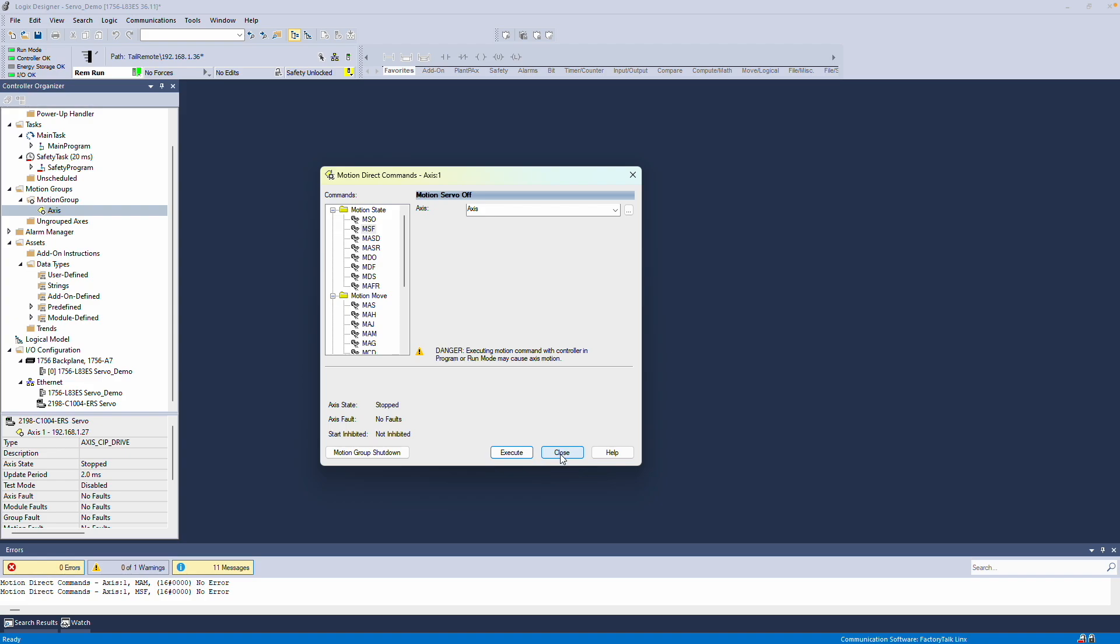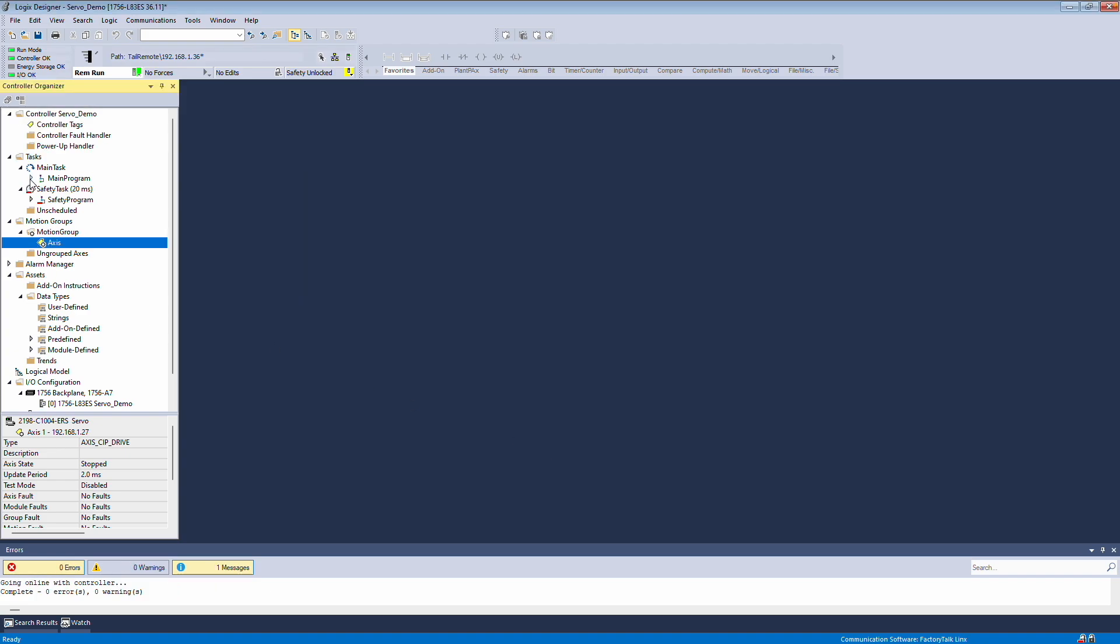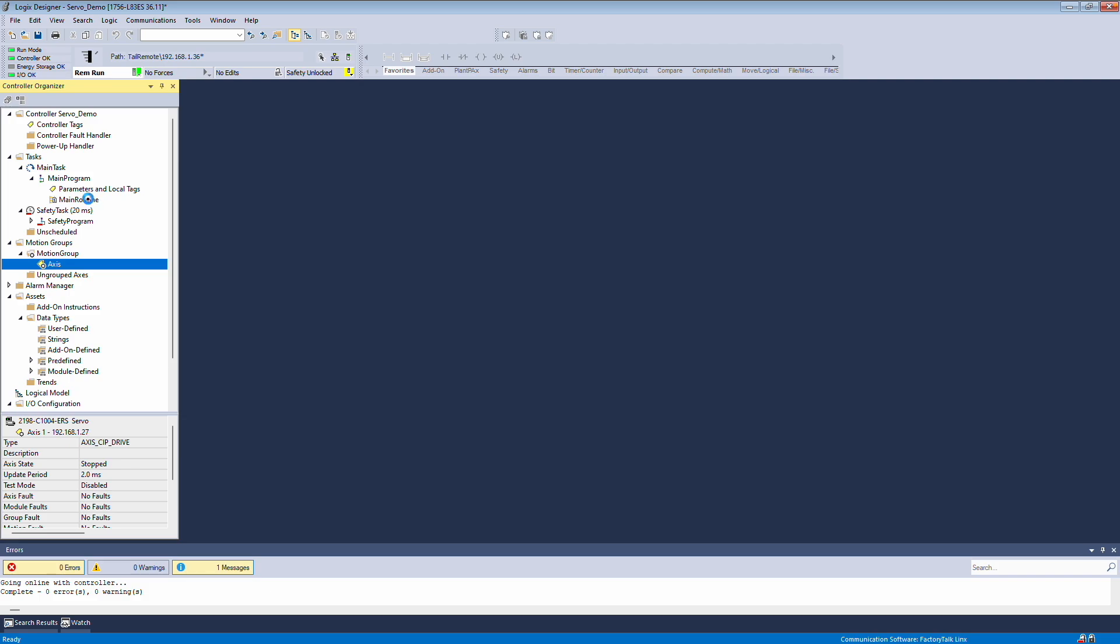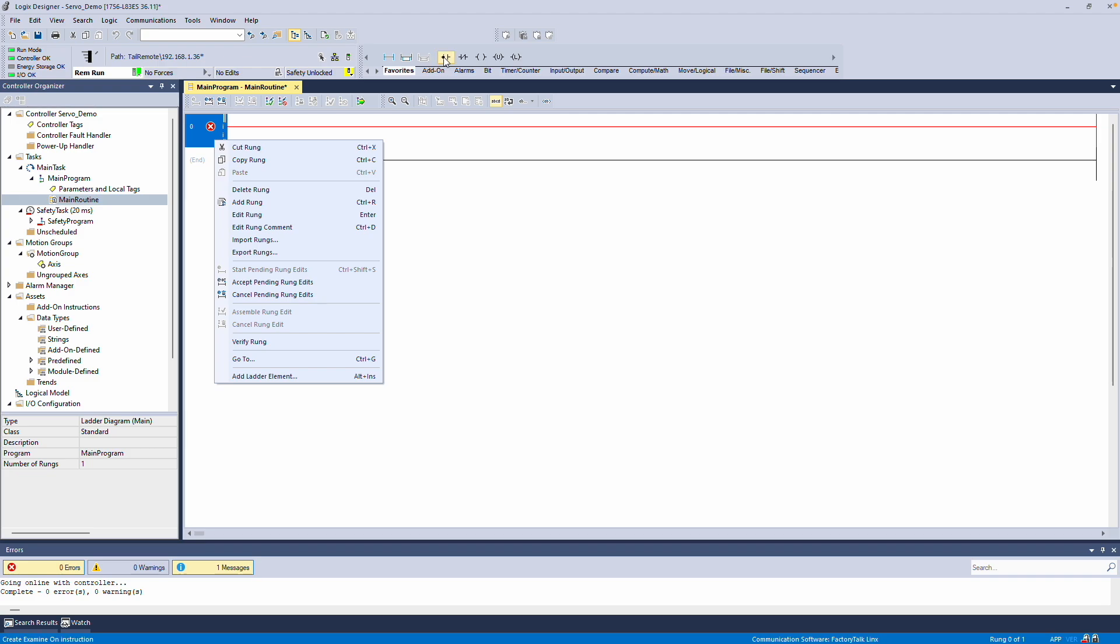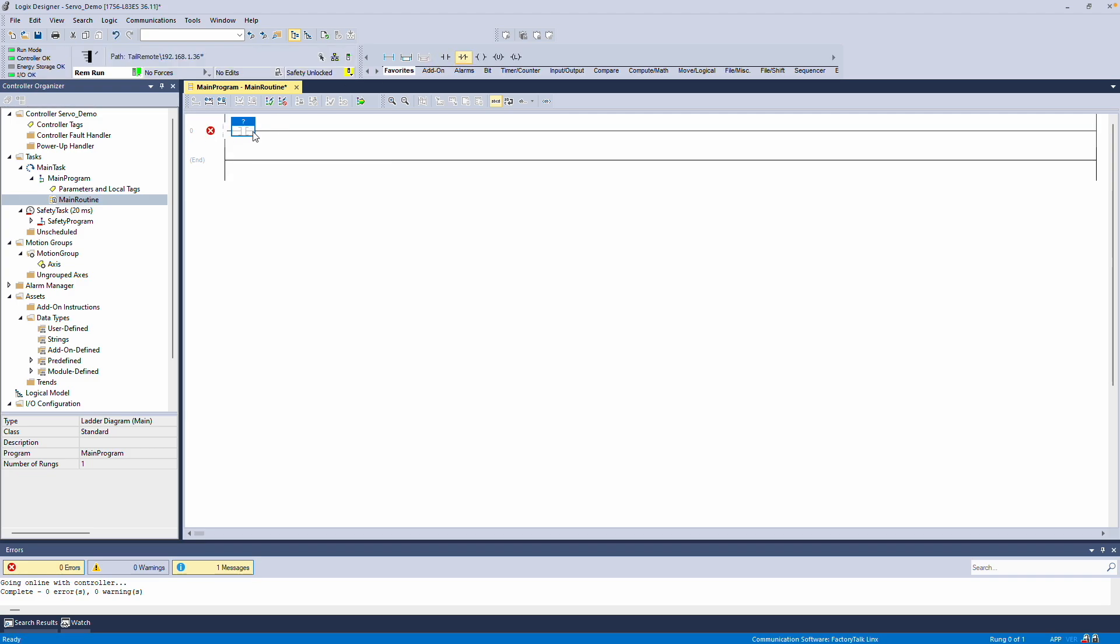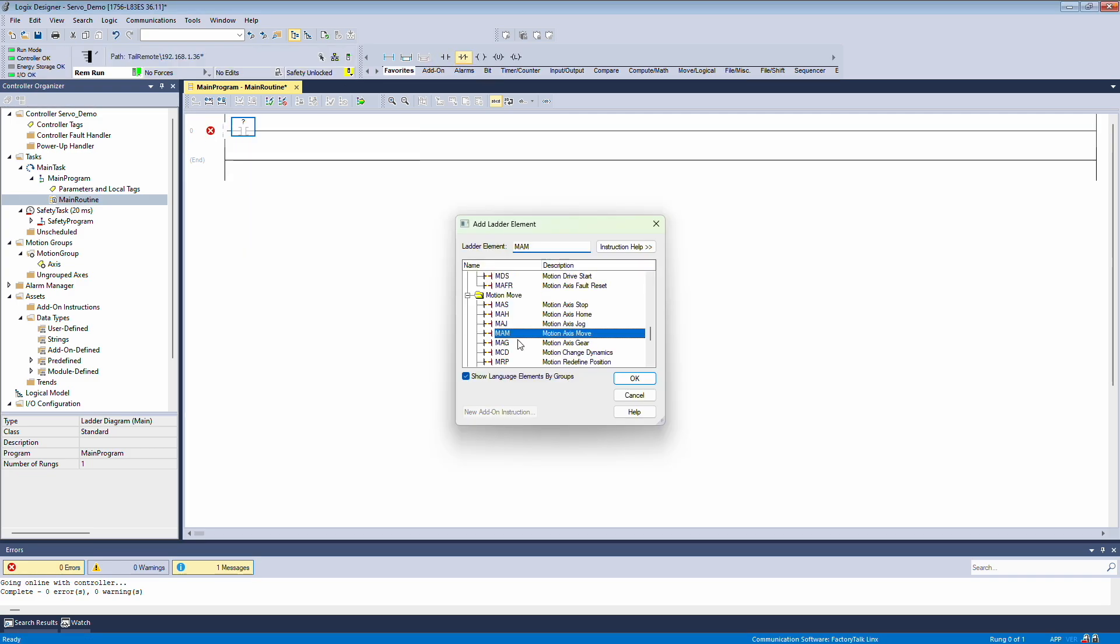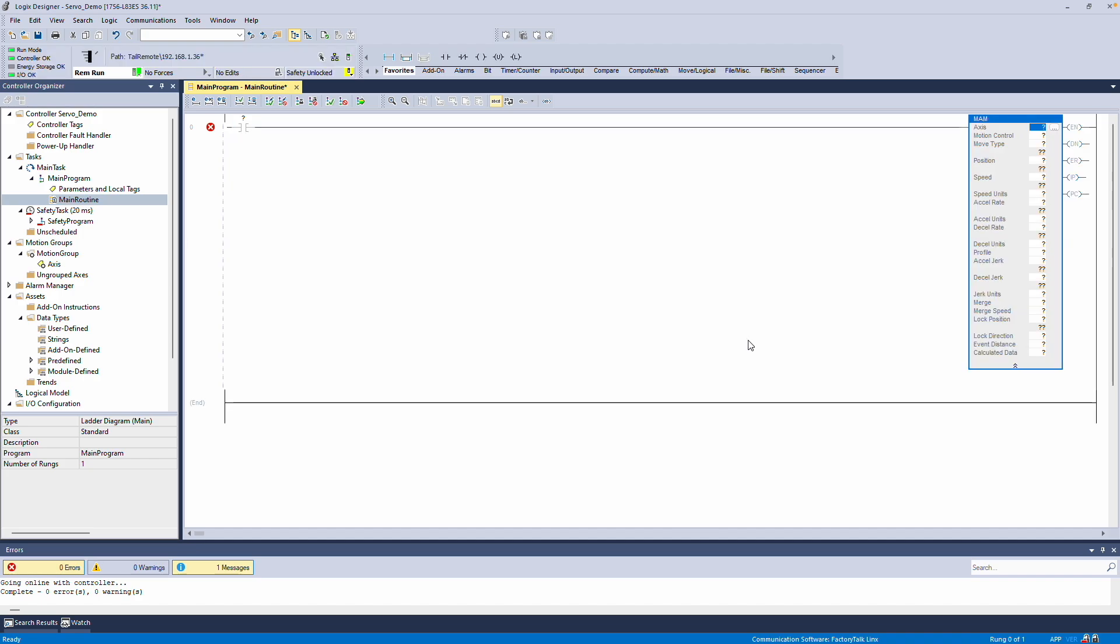Now, let's take a look at some logic. I'll start in the main routine for now. Motion instructions execute every time they are pulsed. So, in this rung, I'll add an Examine If Open instruction followed by a Motion instruction. All the Motion instructions are listed under Motion. We'll use the Motion Axis move that we explored earlier in the Motion Direct commands to build the motion logic.